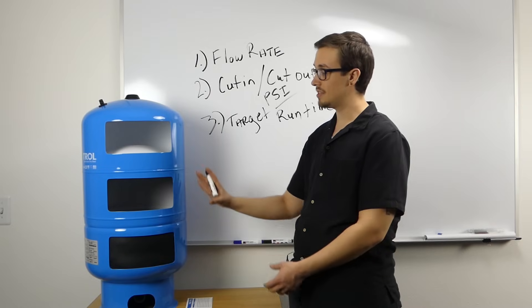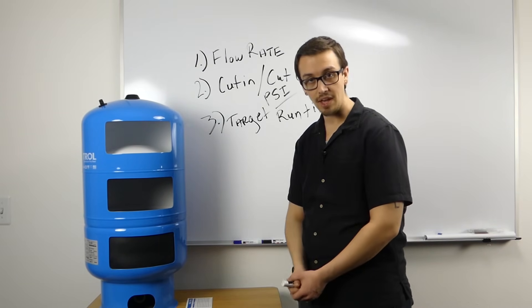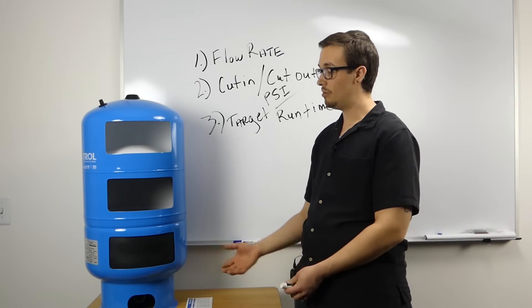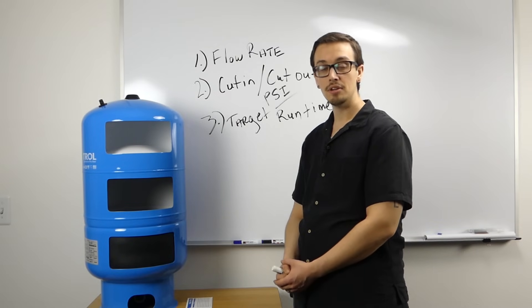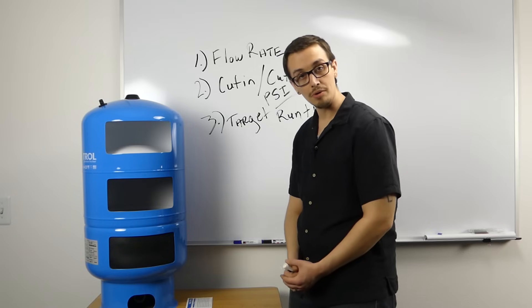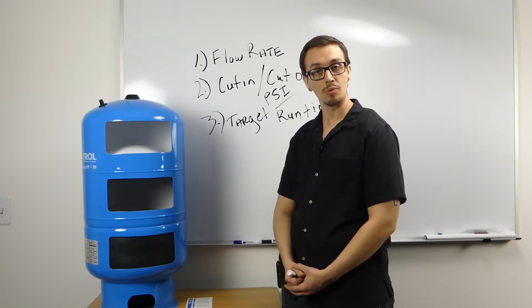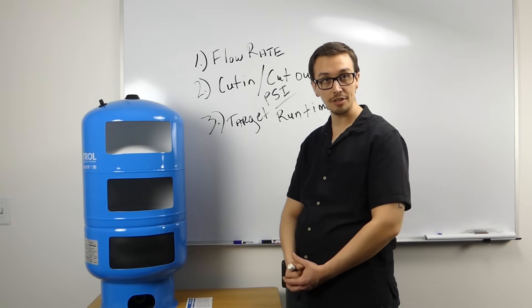Let's imagine that you have a system with this pressure tank and perhaps you've got a five gallon per minute pump. If this pump was in the middle of its drawdown capabilities, let's call that five gallons, your pump would have a one minute runtime. If that pump were below one horsepower, that would be within the recommended target range and this would be an appropriate pressure tank for that application.